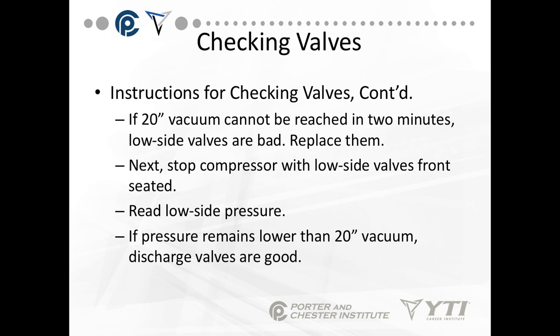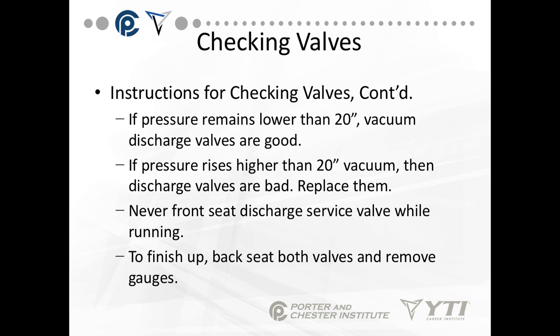Stop the compressor with the low-side valves front-seated and read the low-side pressure. If your pressure remains lower than 20-inch vacuum, your discharge valves are good — we don't want refrigerant coming back through the high side into the compressor. If the pressure rises above 20-inch vacuum, the discharge valves are bad; replace them. Note: we did not front-seat the discharge service valves while the system was running.